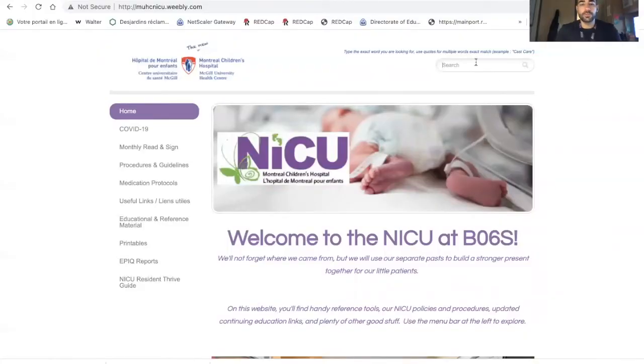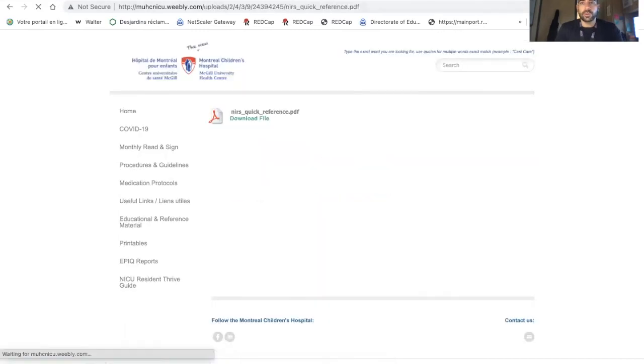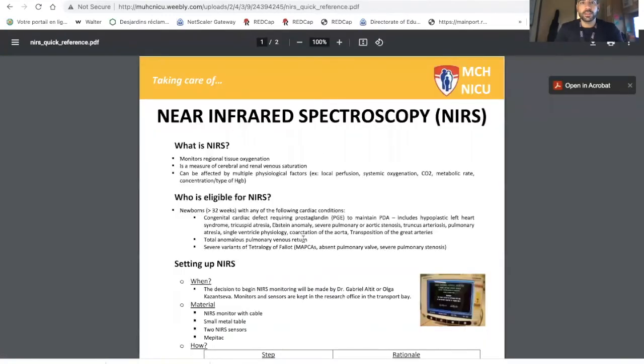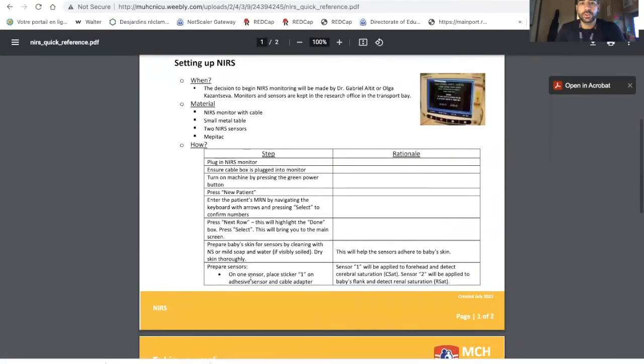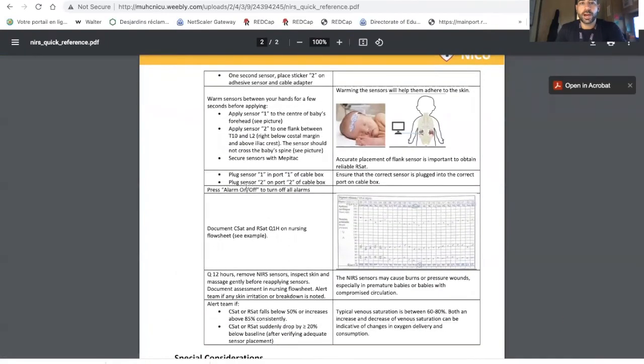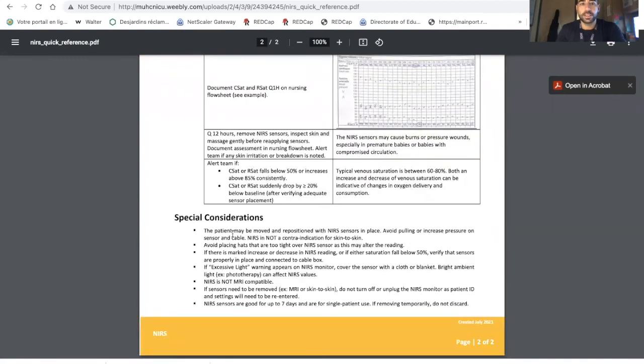On the Weebly, if you search for NIRS, you will find important elements including the NIRS quick reference and the NIRS medical guideline. The quick reference covers what the material is, how to use it, step-by-step instructions, where to put the sensors, how to chart the information, how to notify the team, and special considerations regarding phototherapy — which may cause interference — and the fact that NIRS sensors are not MRI compatible.